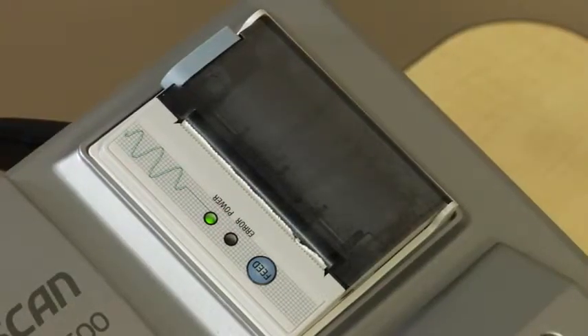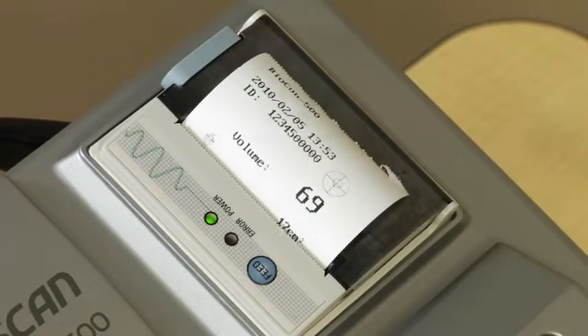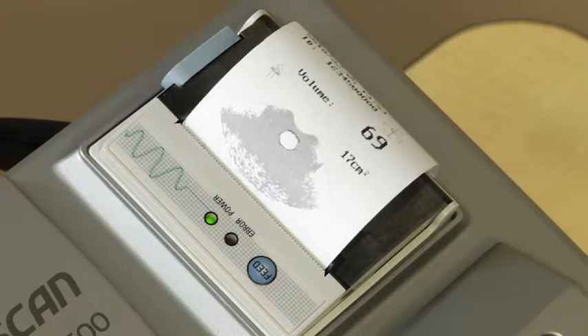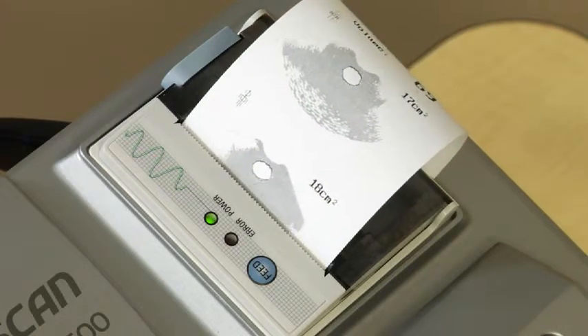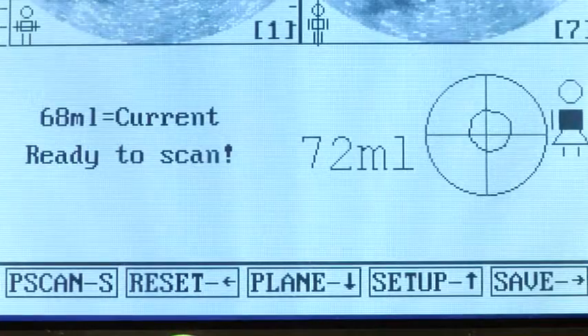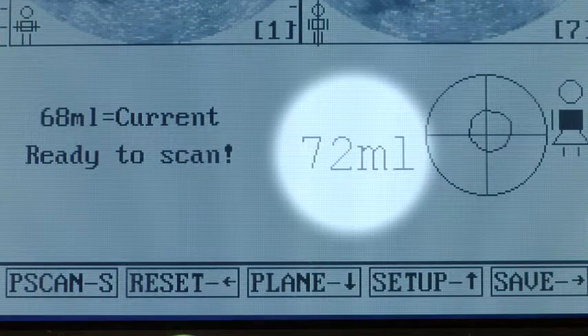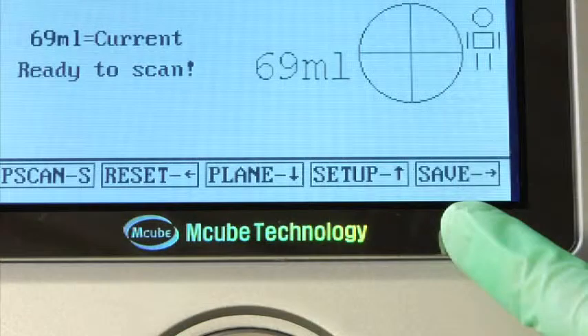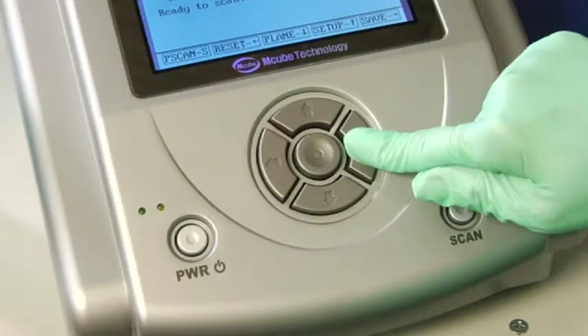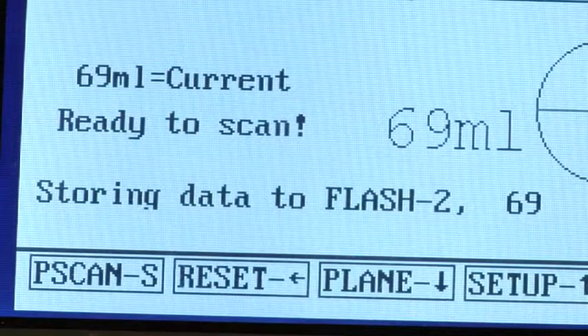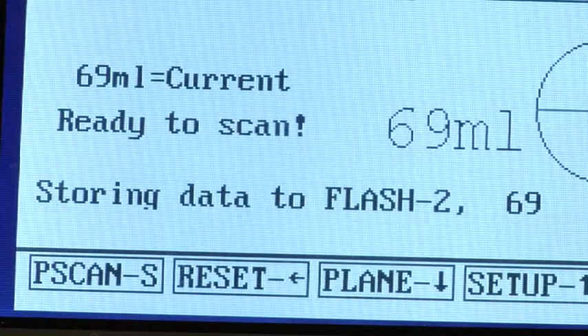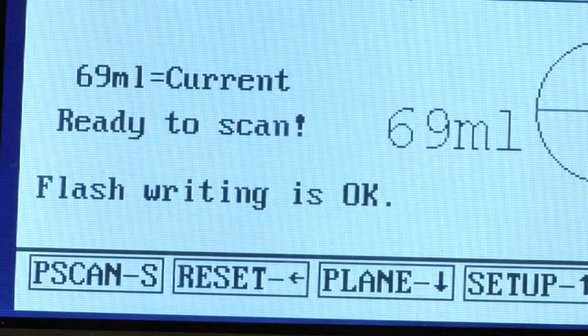Record the measurement. You can also print a copy of the results using the built-in printer and attach the printout to the patient's chart. To print, press the print button. If you scan the patient again, the number that's displayed most prominently on the right side of the screen will always be the largest you've measured, no matter how many times you scan. To save this scan, press the right arrow key, as signified on the screen as Save. Do not touch any other buttons until the screen tells you the scan has been stored to the flash data. The Biocon 500 can hold up to 5 patient scans.